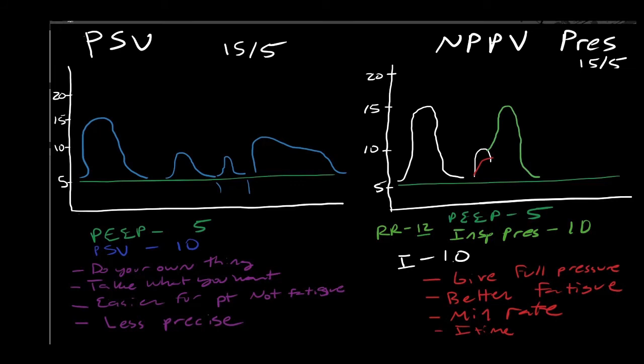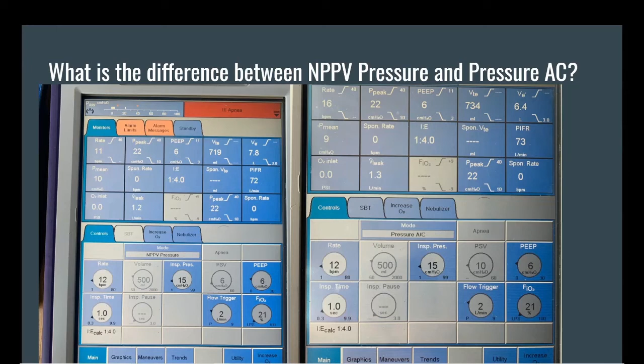Look at our screens and look at the controls. Look at the difference between when you first start up in non-invasive, you start up in NPPV CPAP PSV mode. If you switch it to NPPV pressure, aka BVM mode, and look at NPPV pressure versus pressure AC, you can see that there is no difference. That's why it's like a BVM mode. That's why they're the same things with the same settings.